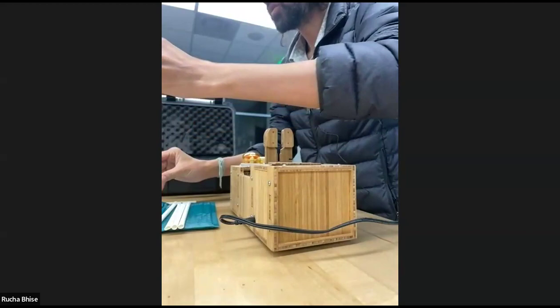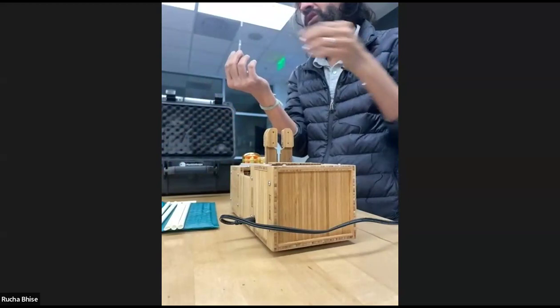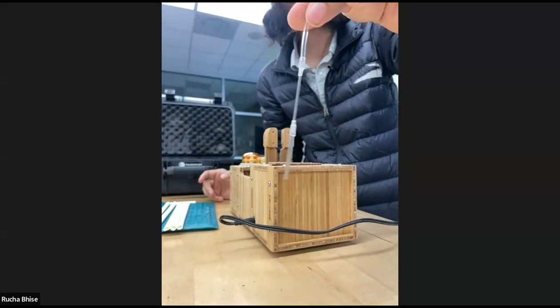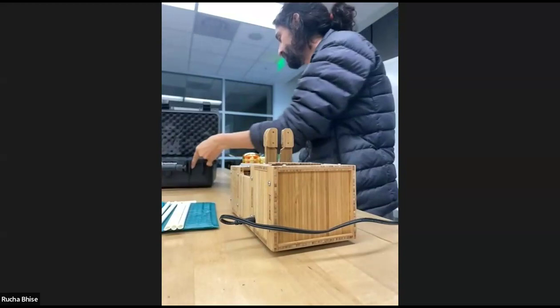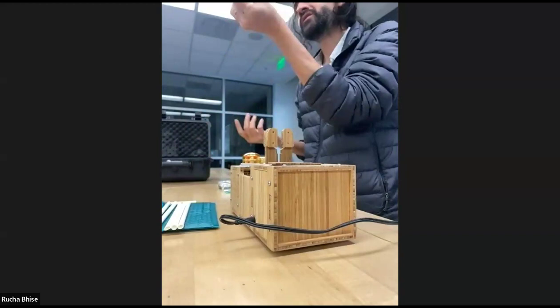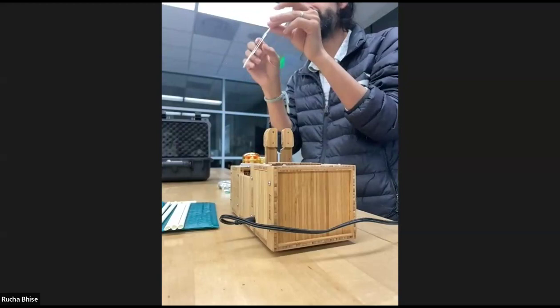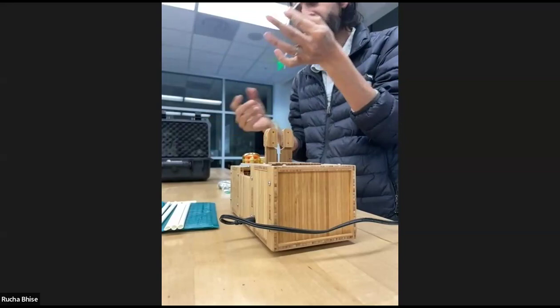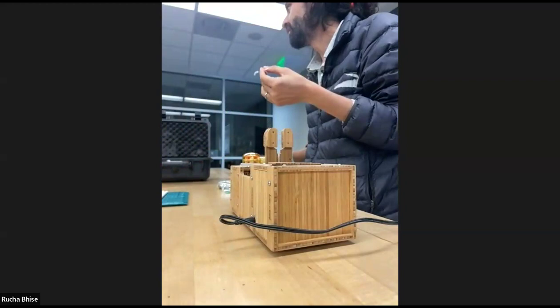You can already identify these are paper straws. This is the imaging chip — the kinds of chips available in the biomedical industry. This is a couple of cents in parts: a glass capillary that's flattened. Traditionally, these imaging chips cost $30–$35 — they're all injection-molded and use-and-throw. There's no plastic in this; it's all glass, so optically it has the best resolution. We use heat shrink — like in electronics with a hair dryer — to cause the seal. So now we have a tube and a seal — that's the imaging chip.